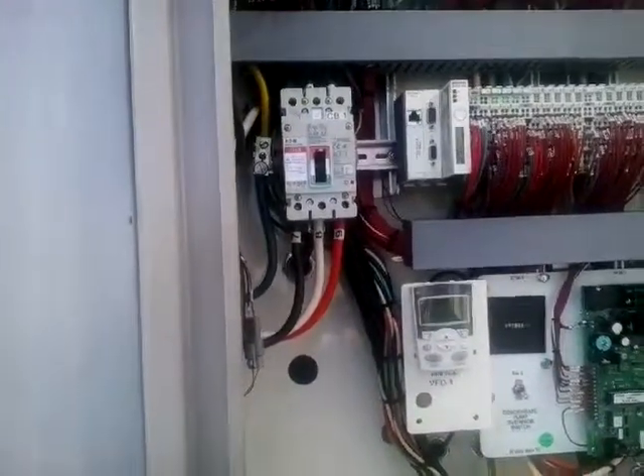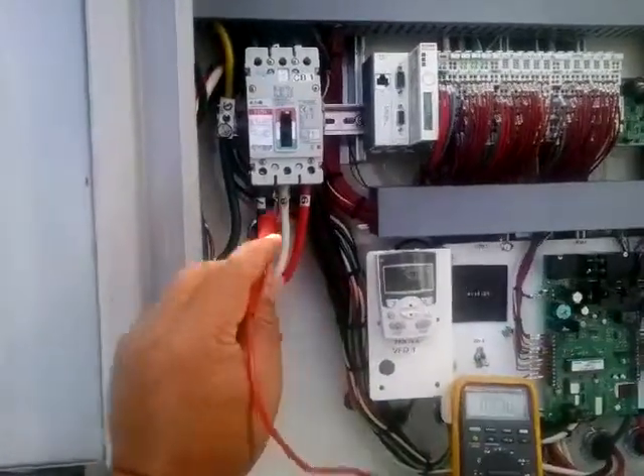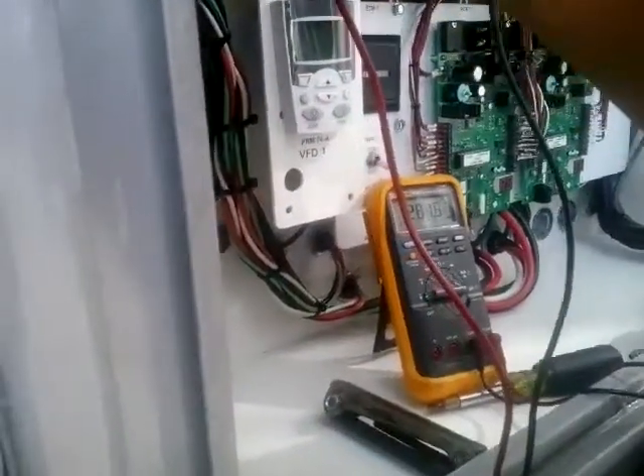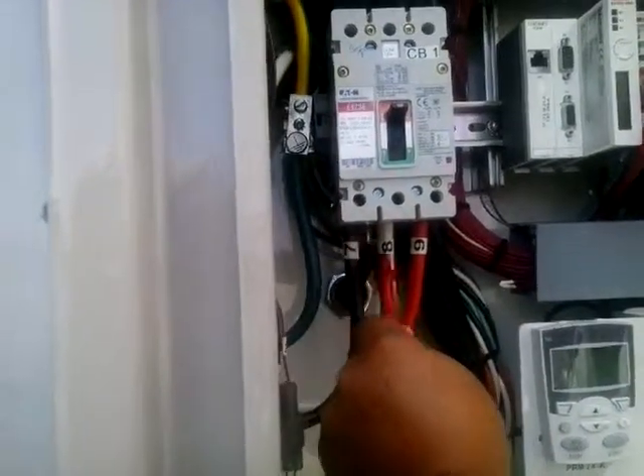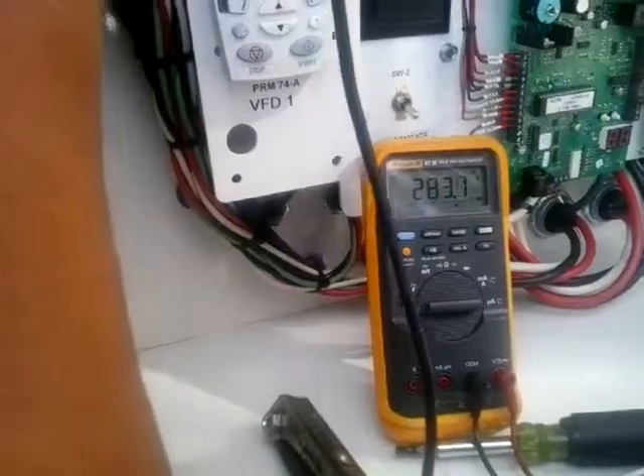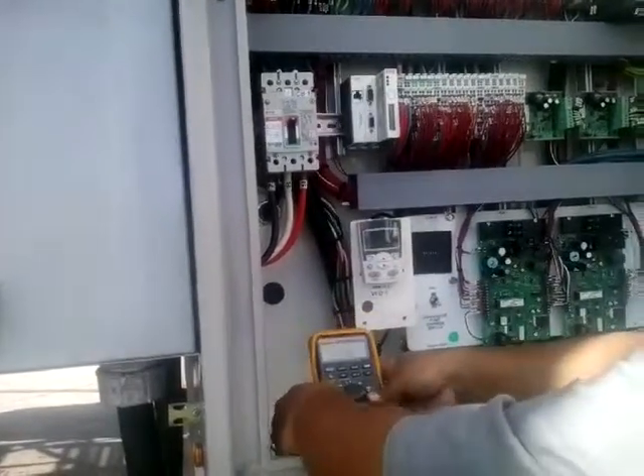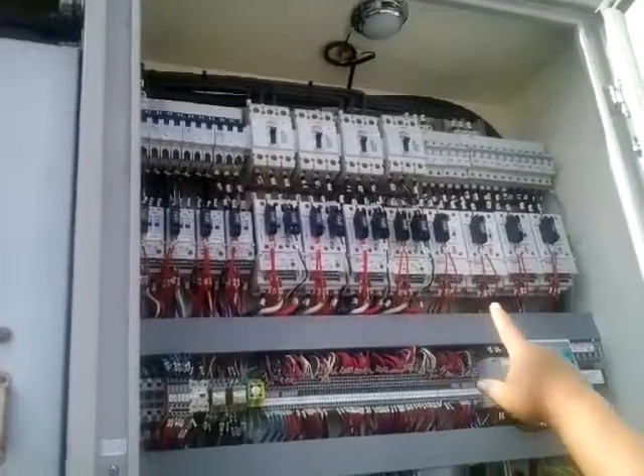Get our multimeter, check power, we got one, check. We got incoming power on the top of CB. And we got power to the bottom. Oh, we also check to make sure none of the breakers are turned off, verifying that they're all on, which they are.